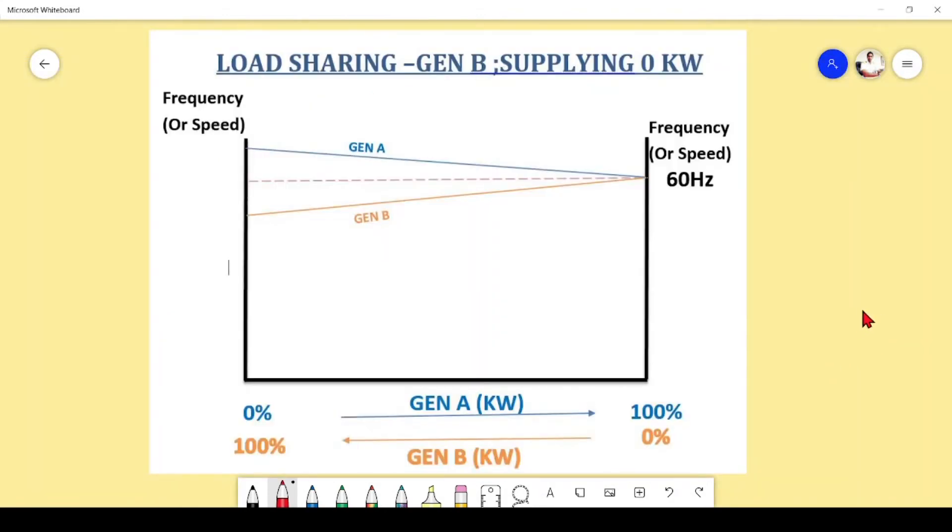So it's clear now how we are going to do the synchronization practically. Now imagine we have already paralleled two generators. That means the incoming generator we have taken into the bus bar, just now connected. There is a graphical representation of these two generators: generator A which was running, and you can see it is running from zero percent to hundred percent load. At that moment, the running generator was taking full load, one hundred percent. Generator B is carrying zero percent load and its load increment is from right to left with hundred percent here. At the moment of connecting the incoming generator to the bus bar, system frequency is 60 hertz, generator A is taking hundred percent load, and generator B is taking zero percent load.